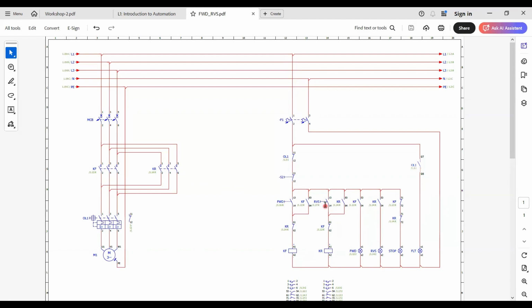Now, if you want to rotate the motor in the reverse direction, you cannot press the reverse contactor. Even though if you press it, it will not allow the reverse contactor to energize, because this point is open now, because KF1 is energized, which leaves this normally closed contact to open. Even though you press, this path is disconnected, that will not allow the reverse contactor to energize.